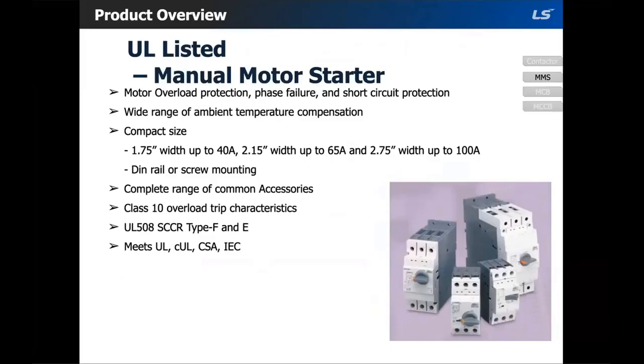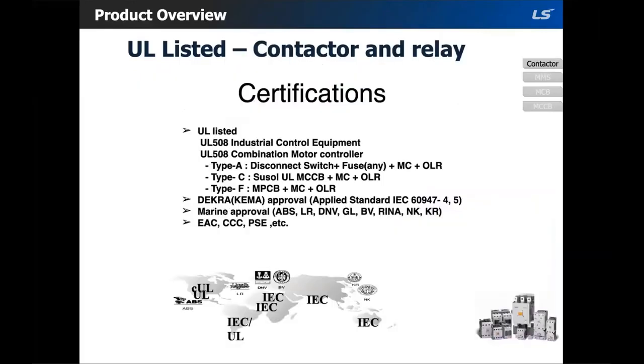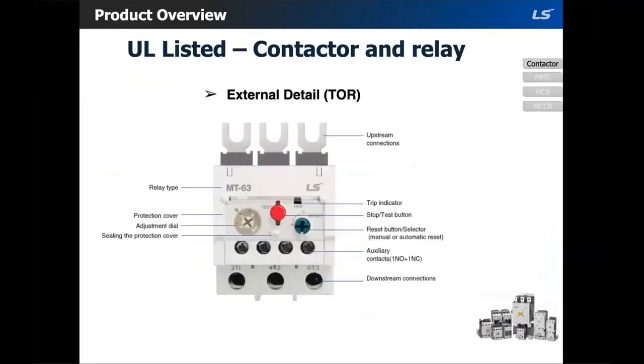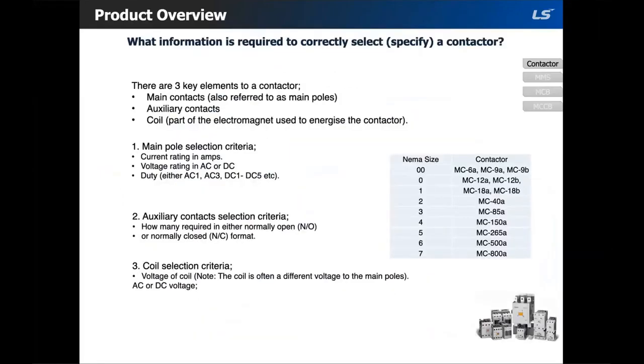Hey, John, if somebody buys a contactor and overload, will it come with a NEMA classification on it? You mean the NEMA size? Correct. Yeah, so on the nameplate there should be a NEMA size. I also included a NEMA size table in the slides here. It's not going to be on the overload, it would be on the contactor, I believe. I was asking for clarification because a lot of people want to know if LSIS is a NEMA rated starter. And I know the ones that I have seen used in starter applications have that NEMA rating on it. I just wanted you to confirm that.